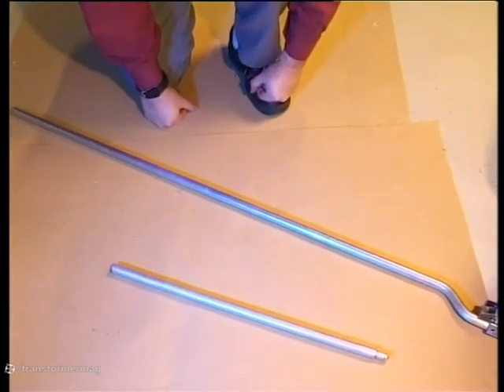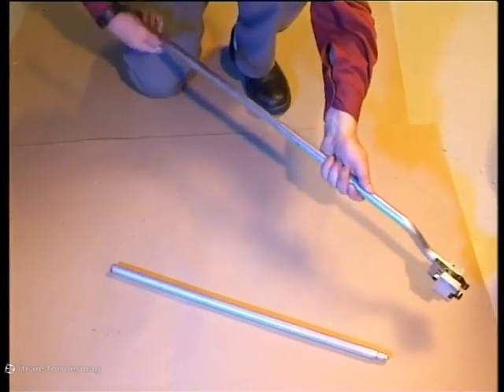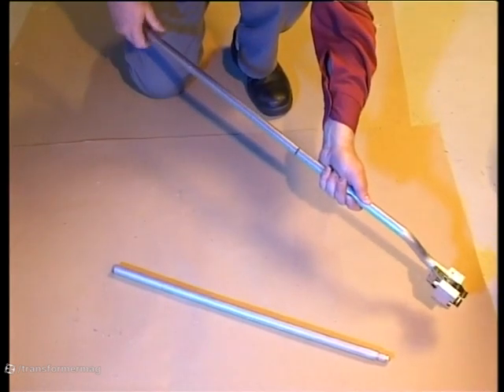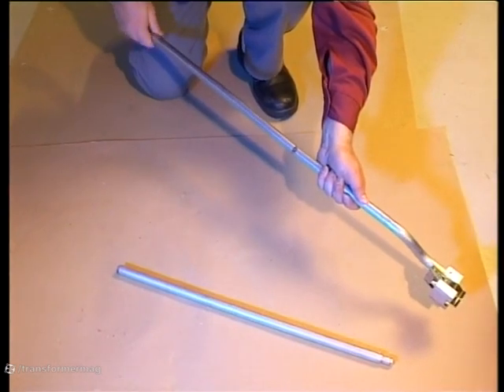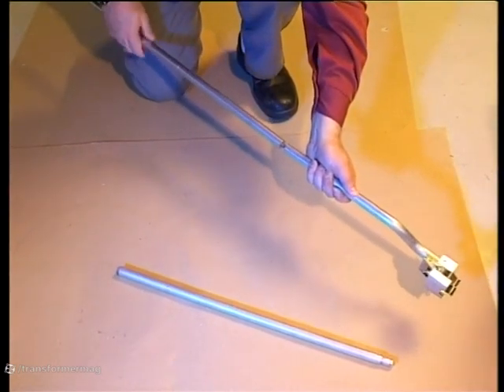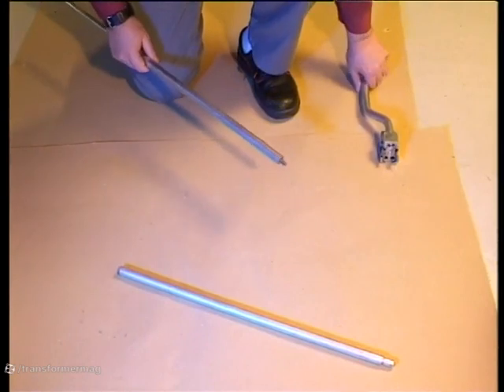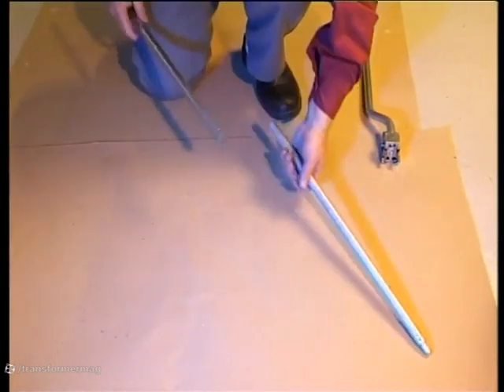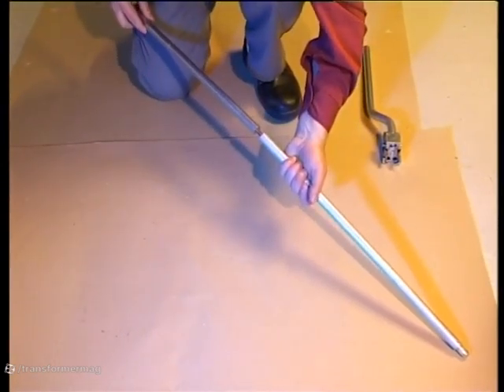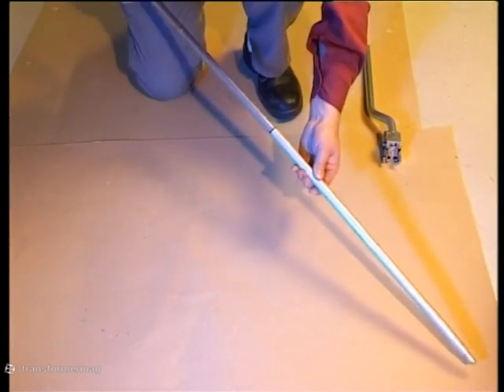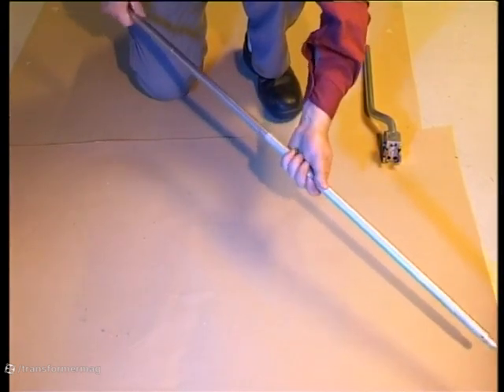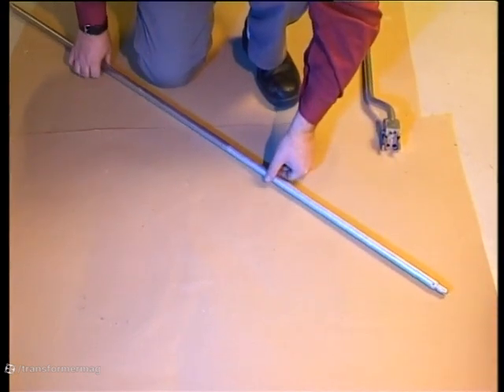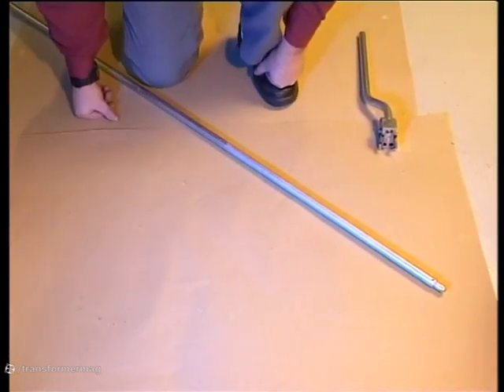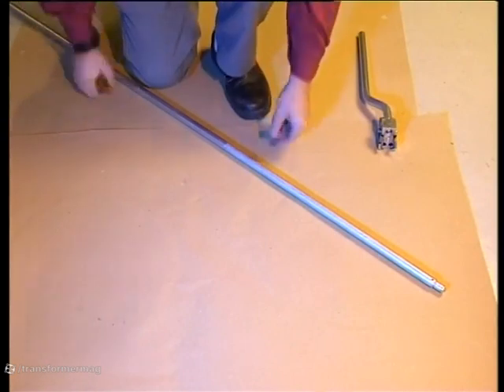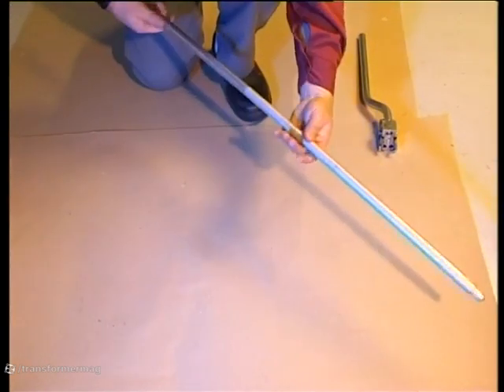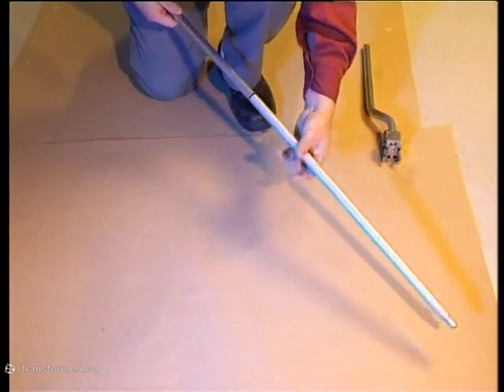If you're working with a tap changer which has a letter T as the last letter of its type designation, you'll need the entire length of the tool. This refers to a fully insulated on-load tap changer. If you're working with a tap changer with N as the last letter of its type designation, which is a neutral point version, leave out the short part of the tool.